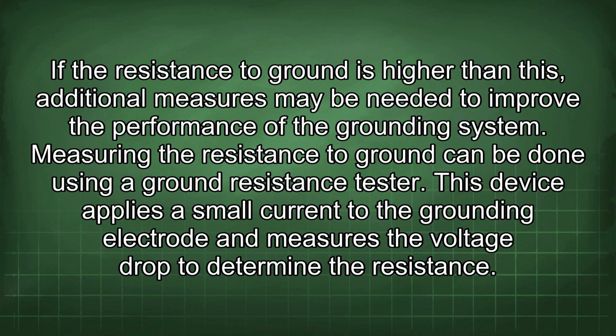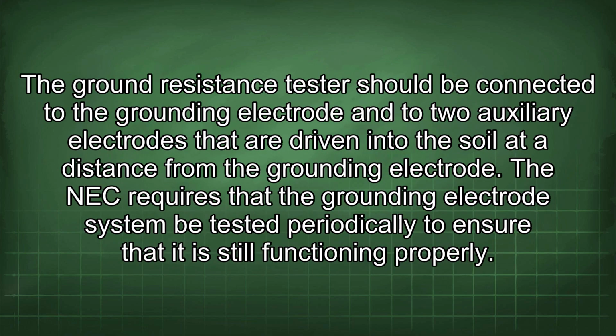If the resistance to ground is higher than this, additional measures may be needed to improve the performance of the grounding system. Measuring the resistance to ground can be done using a ground resistance tester. This device applies a small current to the grounding electrode and measures the voltage drop to determine the resistance. The ground resistance tester should be connected to the grounding electrode and to two auxiliary electrodes that are driven into the soil at a distance from the grounding electrode.